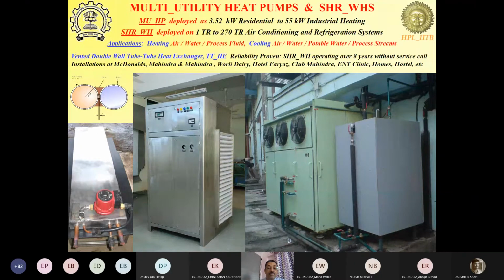So earlier they were using electric heaters. So compared to electric heaters, if the COP of the heat pump is 3, then we were saving 66% energy. If the COP was going up to 4 also in some circumstances, then we are saving 75% of the energy that the client was earlier using. And not only that, in addition to that, we were giving free cooling, because the unit was kept in the plant room and it would suck air, filter it, cool it, dehumidify it, recover the heat from that, and then that heat was delivered in the condenser of the heat pump after the compressor had done some work on it. So we had to supply the compressor work, and then the condenser heat would be tapped out for this using the tube-tube heat exchangers.